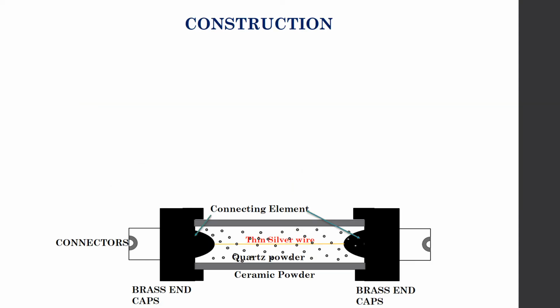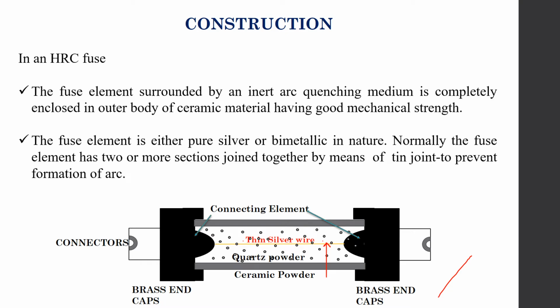Construction. Looking at the construction, the figure here depicts the inner view of an HRC fuse. In an HRC fuse, the fuse element represented here by the yellow line is either pure silver or bimetallic in nature. Generally, this fuse wire is not a complete wire, but it is made up of various sections joined together by means of tin joints. This is done to prevent the formation of arc when the wire breaks due to overcurrent, or current exceeding the predetermined value. Also, this fuse element is surrounded by an arc quenching medium. It can be either quartz powder or silica sand, used as an inert arc quenching medium here.